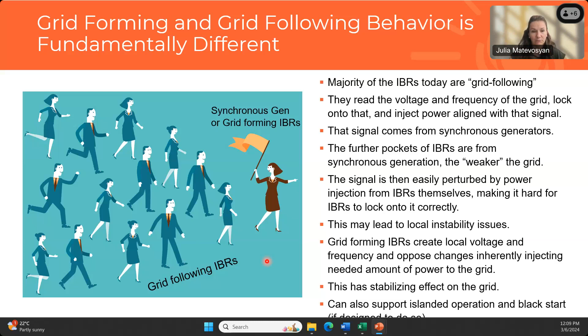So grid forming inverters is kind of advanced control strategies for inverter-based resources that create local voltage and frequency and oppose changes inherently injecting needed amount of power to the grid. This can have stabilizing effect on the grid, and it can also support islanded operations. So for example, if the grid splits into smaller islands and they still can operate stably and reliably, and providing black start capability, but this requires special design considerations for an IBR that are above and beyond just overall interconnected grid operation.